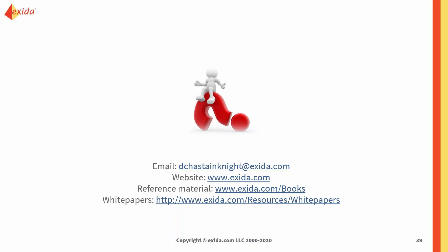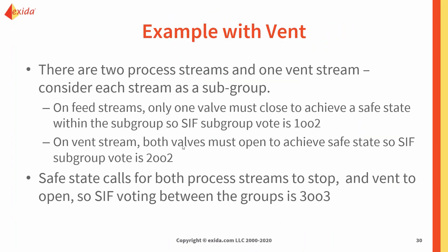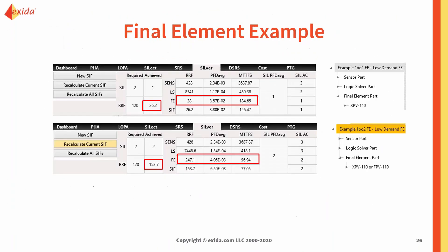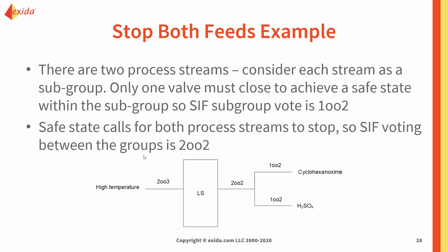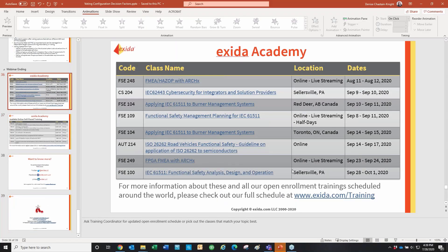Question: The calculated RRF is 107 — is it not close enough to a risk reduction factor of 120 to pass? No. Our target risk reduction factor is 120, not 112. So 107 is less than 120 and does not meet the target.